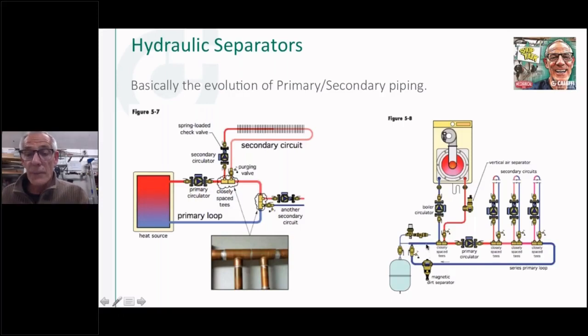Now, the other thing that came up, and Dan Holohan helped me out with this, I said, which is the primary and which is the secondary? This seems to be confused in a lot of people's minds. I always thought, well, if it's the boiler, it's the primary. It's the hotter, that's the primary. And Dan said, well, Gil intended it to be wherever you connect the expansion tank develops the primary loop. So in this case, with the expansion tank connected in here, that becomes a primary loop, even though a lot of people say, well, no, it's always the loop with the boiler. And from my understanding, it's the expansion tank connection that establishes that.